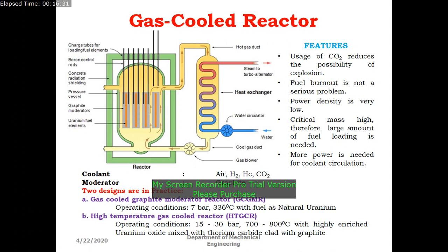Now the gas itself is also circulated from the top to a heat exchanger. In the heat exchanger, the heat available in the hot gas is rejected to the water which is coming from the steam condenser. The water gains the heat and converts into hot steam. The steam is expanded in the steam turbine, which can produce power output.